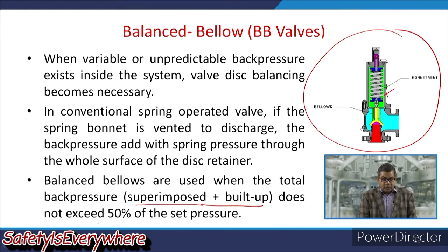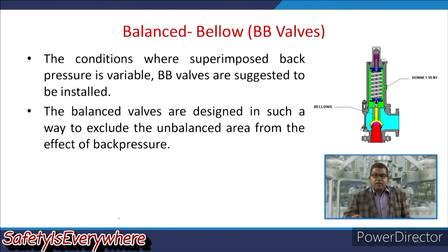Now balanced bellows are used when the total back pressure, that is the superimposed plus built up, does not exceed 50% of the set pressure. Where the superimposed back pressure is variable, these balanced bellow valves are suggested to be installed. The balanced valves are designed in such a way to exclude the unbalanced area from the effect of back pressure. Now these are the bellows, you can see.